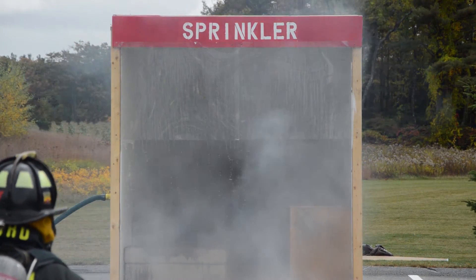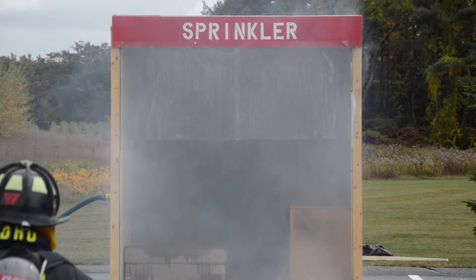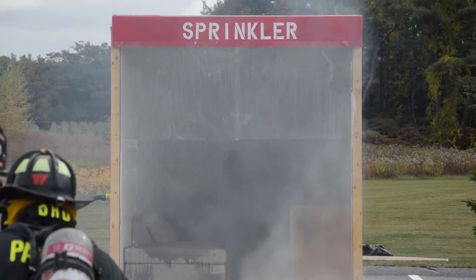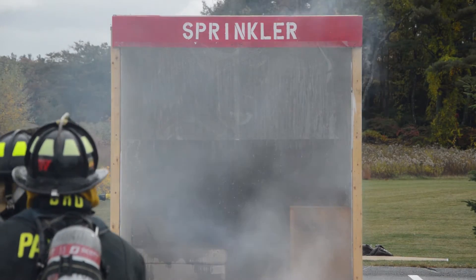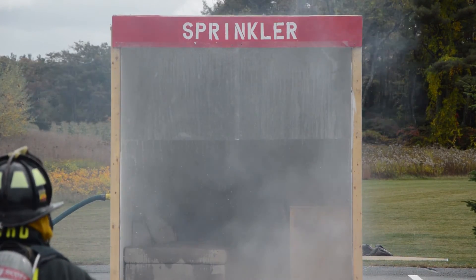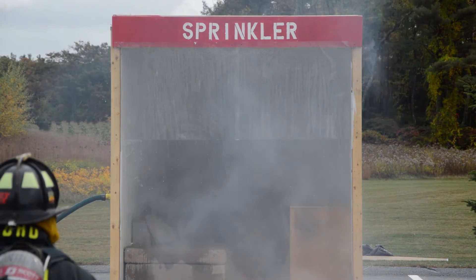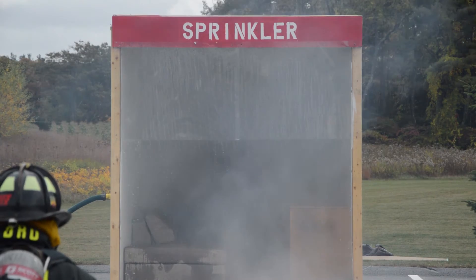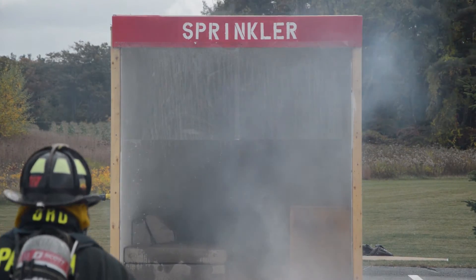As you can see, the sprinkler is still producing a lot of smoke but the fire is being brought down with the water. That fire already went through the incipient stage, barely reached the growth stage, never got to be fully developed, and now it has certainly gone into the decay state. Very good — the water has put it out.